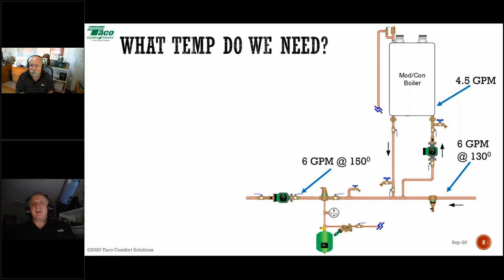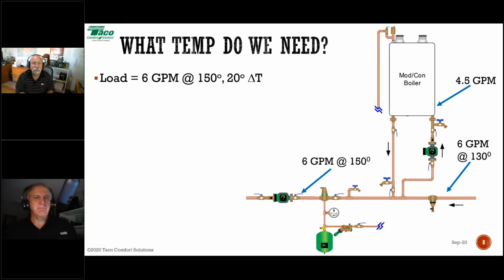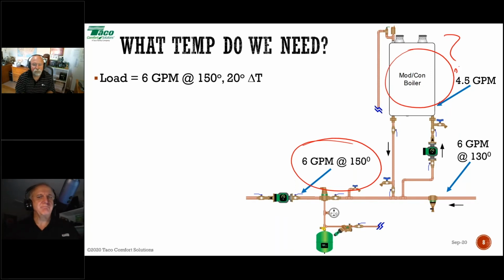All right, very good. I want to go over a little example here of what temperature we might need. So let's say, and I think I'm going to have a couple of different numbers here, but what I want to figure out is if I have a specific temperature requirement on my system going out to my heating system, what temperature does the boiler have to make? In this example, I've got 6 gallons a minute at 150 degrees that I need for my heating system. What temperature does the boiler have to make in order to give me that 6 gallons per minute at 150 degree water?